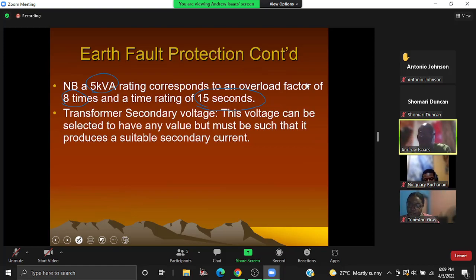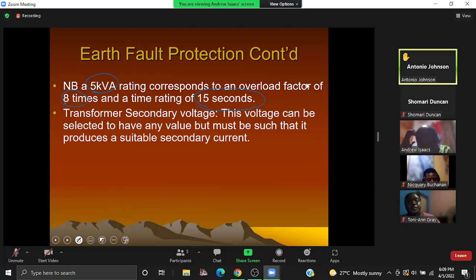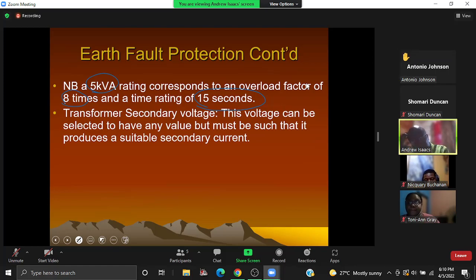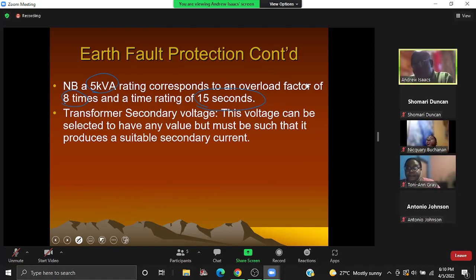So remember now, that's just the rating of the transformer. Yes, Mr. Johnson. I was saying that this would still be sufficient based on the time that the relay would take to clear faults in most instances. Yes. So that's the justification you would use in selecting the 5 kVA. All right?